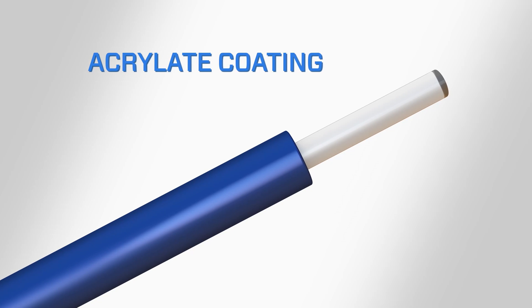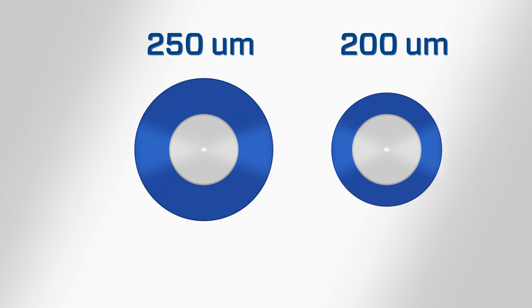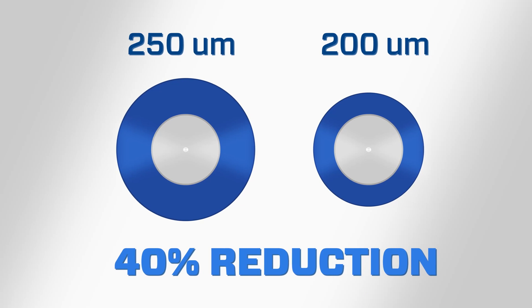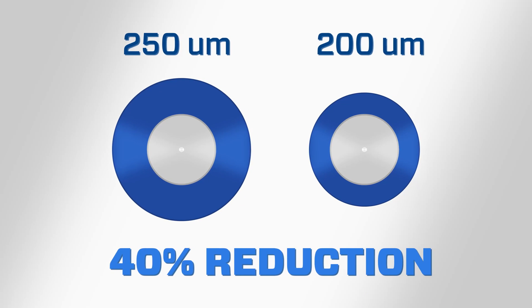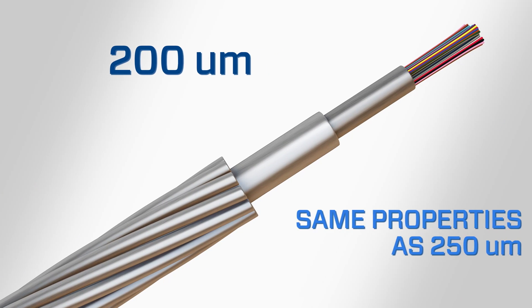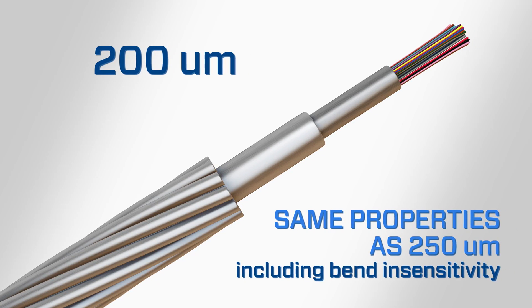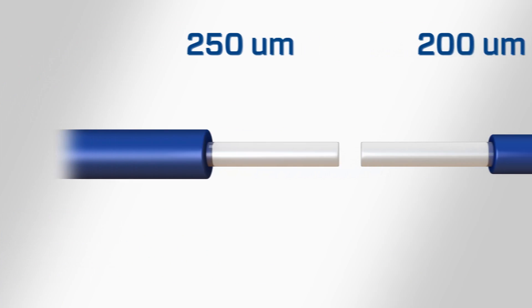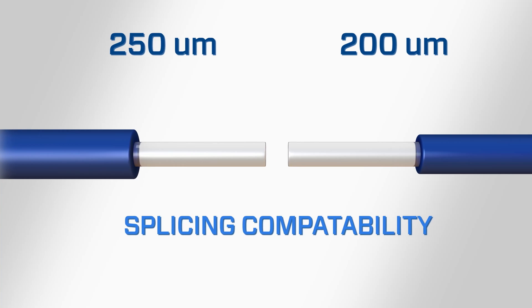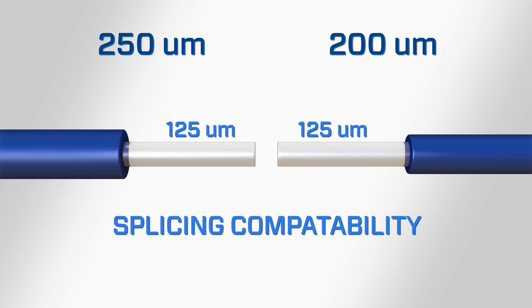In a traditional optical fiber, the coating has a diameter of 250 microns. Advances in fiber manufacturing processes have allowed coatings of fibers to be reduced 40% in size to 200 microns, while maintaining the same core and cladding diameters. This allows the 200-micron optical fiber to retain the same properties, including bend insensitivity, as the latest 250-micron single-mode fibers. This also means that there is compatibility with splicing — when the coating is stripped away, you will be splicing 125-micron diameter glass to 125-micron diameter glass.